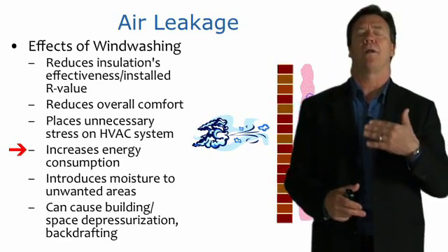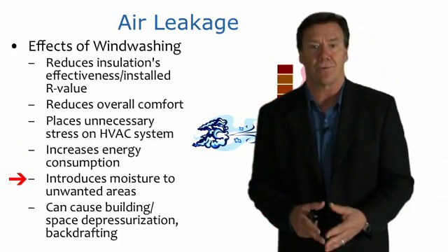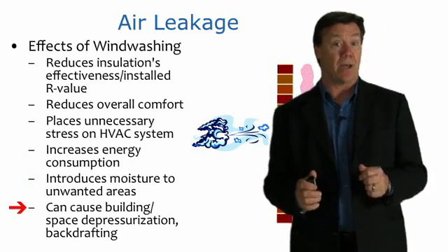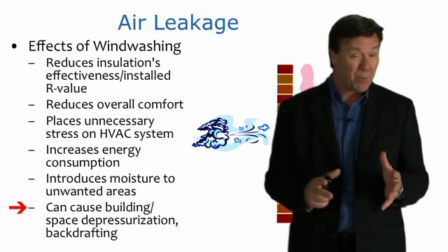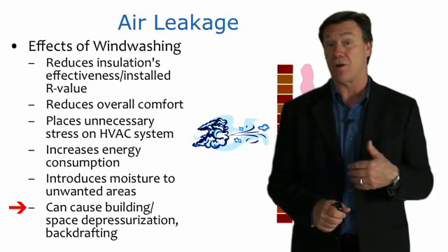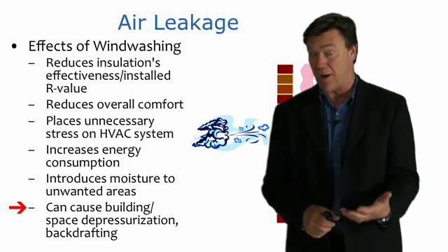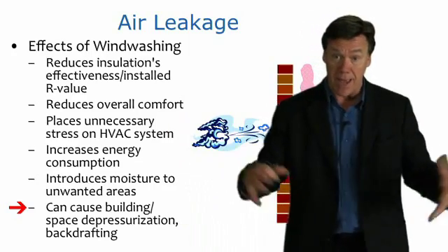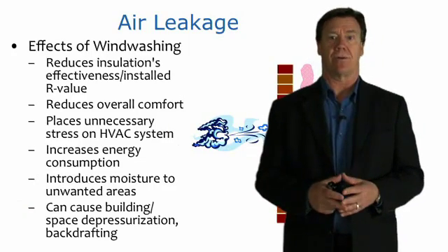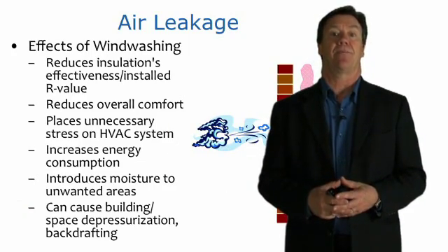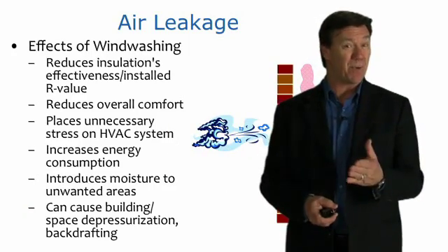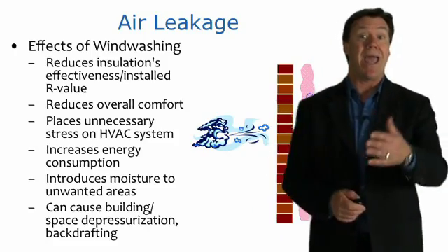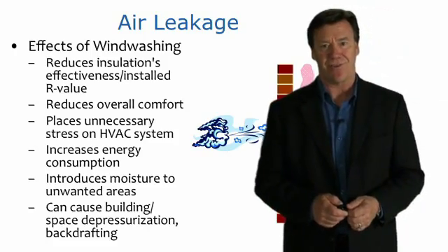Air leakage causes unwanted moisture infiltration and can cause buildings to be under negative pressure, which can cause combustion appliances like fireplaces and water heaters to backdraft. When a structure is under negative pressure, that's a problem in terms of life safety, as well as moisture and energy efficiency.